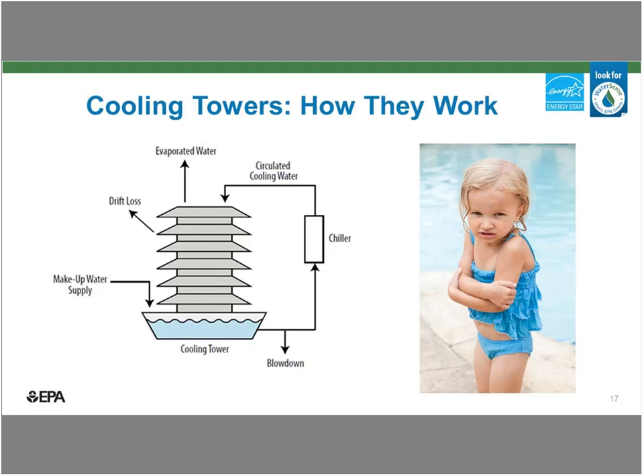This is by design and is the purpose of the cooling tower. Some quantity is lost to small droplets called drift, although this is generally pretty small. Some water is then discharged as blowdown to keep minerals from building up in the recirculating cooling tower water. And lastly, makeup water is added to balance the losses that occur due to evaporation, drift, and blowdown.